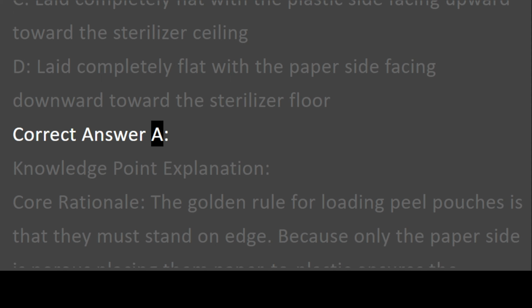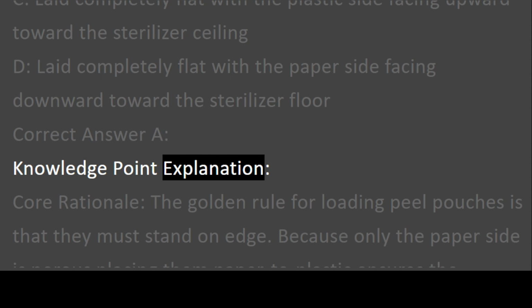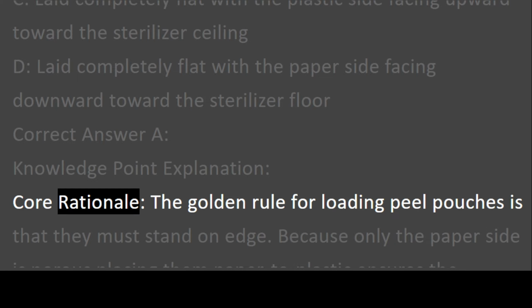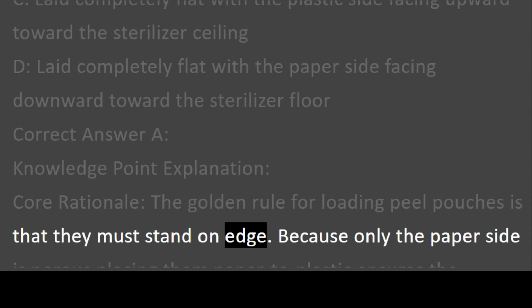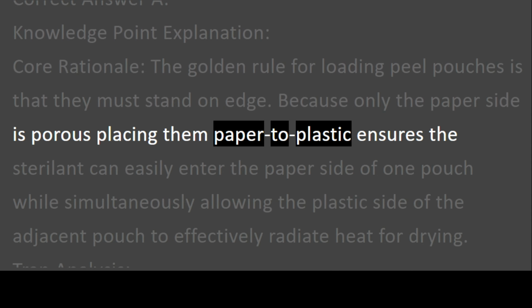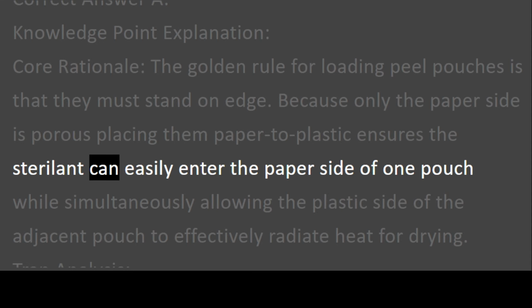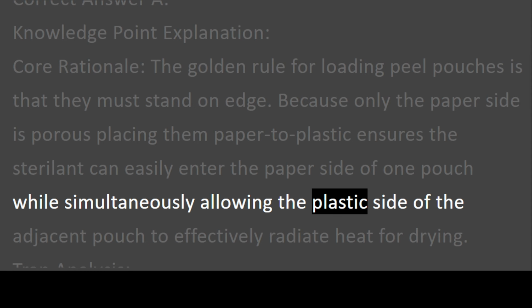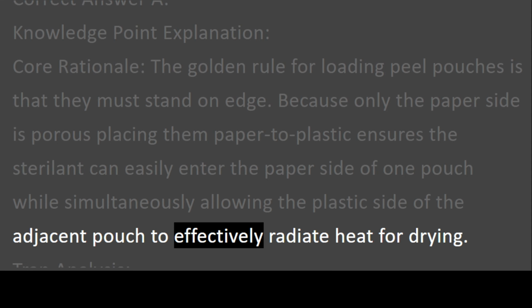Correct answer A. Knowledge point explanation. Core rationale. The golden rule for loading peel pouches is that they must stand on edge. Because only the paper side is porous, placing them paper to plastic ensures the sterilant can easily enter the paper side of one pouch while simultaneously allowing the plastic side of the adjacent pouch to effectively radiate heat for drying.